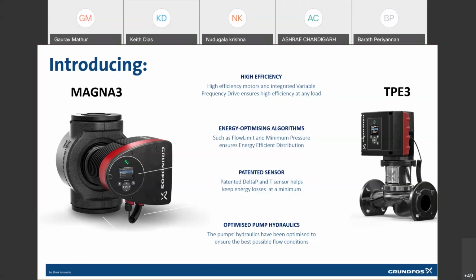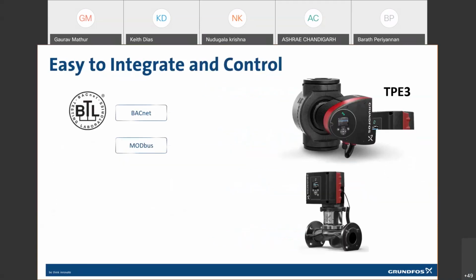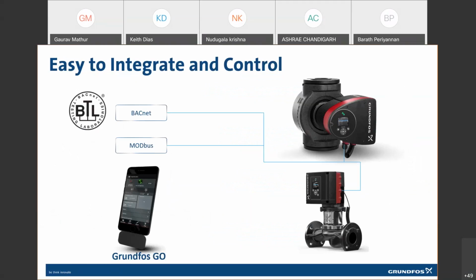This is made possible with the help of the pump hydraulics which we have changed, plus the advancement in the kind of motors which we are using. So it is the change in technology which has made this possible. Another important and very strong point is that distributed pumping is a strong platform for digitalization. There is a communication network possible under different protocols, whether it is BACnet or Modbus, and the entire data from the pump can be taken to a management system. A host of data can be recorded, and we can then generate patterns for optimization.